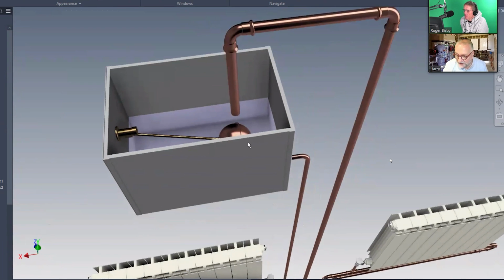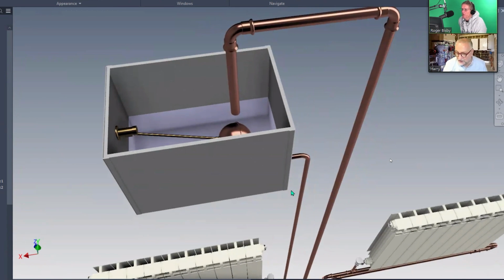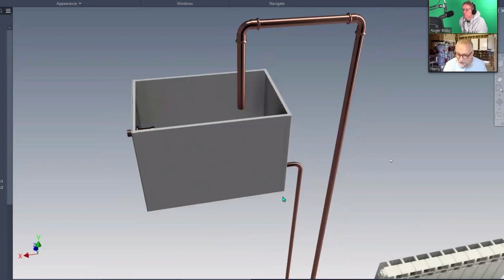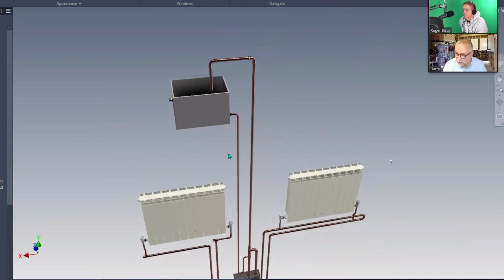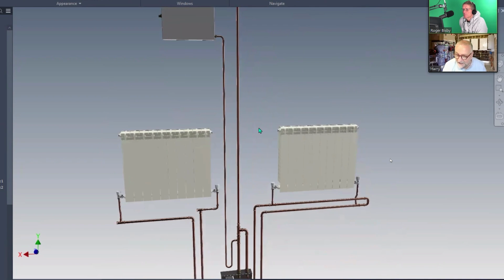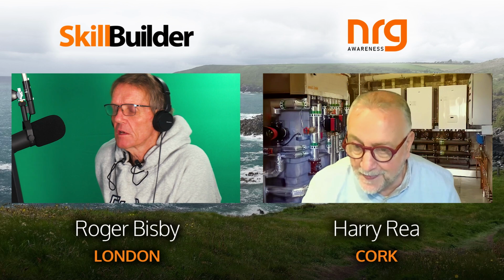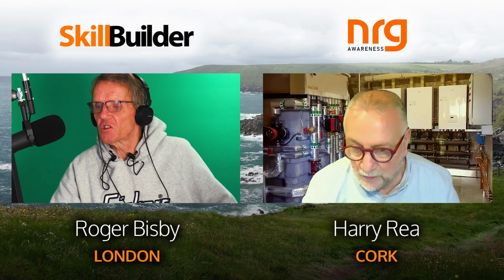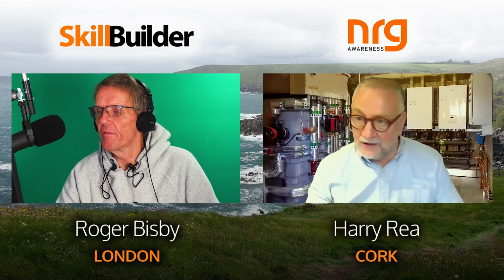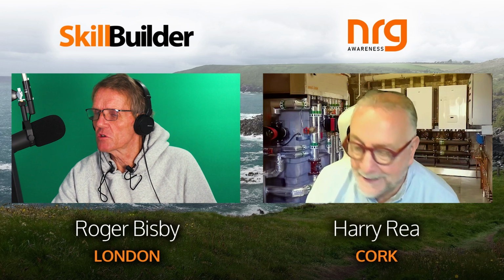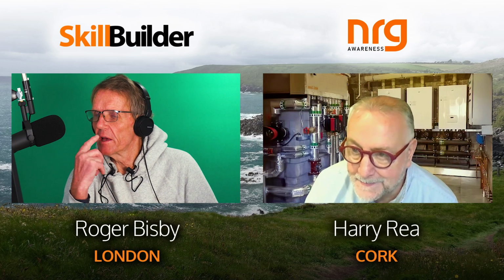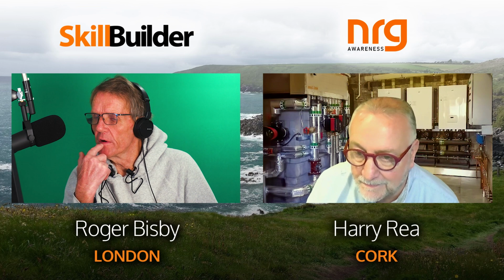Yeah. With this system, it's sucking in or it's blowing out, is what you're saying. Yeah. Whereas with this system, it doesn't budge. There's no movement in the attic. So when people are saying putting tall expansion pipes, that's 100% wrong, because it shouldn't be moving in the expansion pipe. If it's moving in the expansion pipe, your system's going to rust. That's interesting, because I've done that. Extended the expansion pipe up, the vent pipe up, if you like. Let's call it the vent pipe. Extended that up to stop the pumping over, as we call it here.